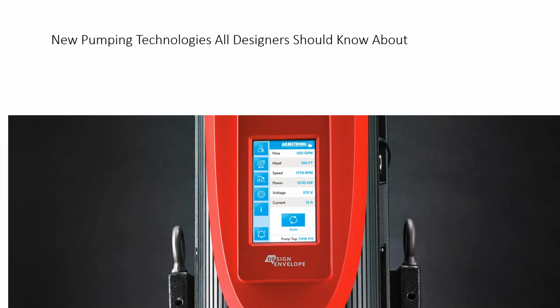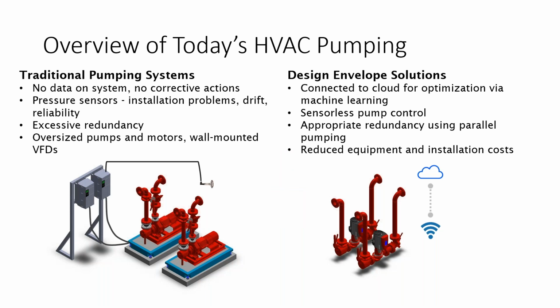So, new pumping technologies all designers should know about. This is a design envelope with Armstrong pumps. With our pumping technology today, we have traditional pumping systems, which have no data on the system, no corrective actions, pressure sensors with installation problems, drift, and reliability issues, also excessive redundancy, oversized pumps and motors, and then wall-mounted VFDs. Very expensive installations, and oftentimes we don't get those pressure sensors in the right locations, right?